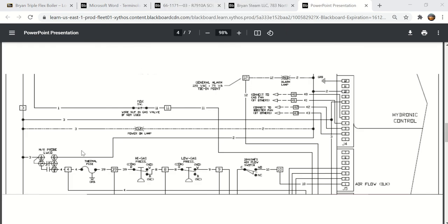Okay, so back to the wiring diagram. Here you see power coming in to terminal 1 or H, and I know they give dual designation for all these terminals because there are two different brands or manufacturers of low water cutoffs that they use. Some of the manufacturers, this terminal here is called H, some of them it's called 1. So that's where you see the 1 over the H, 2 over the N. This is either neutral or terminal 2.